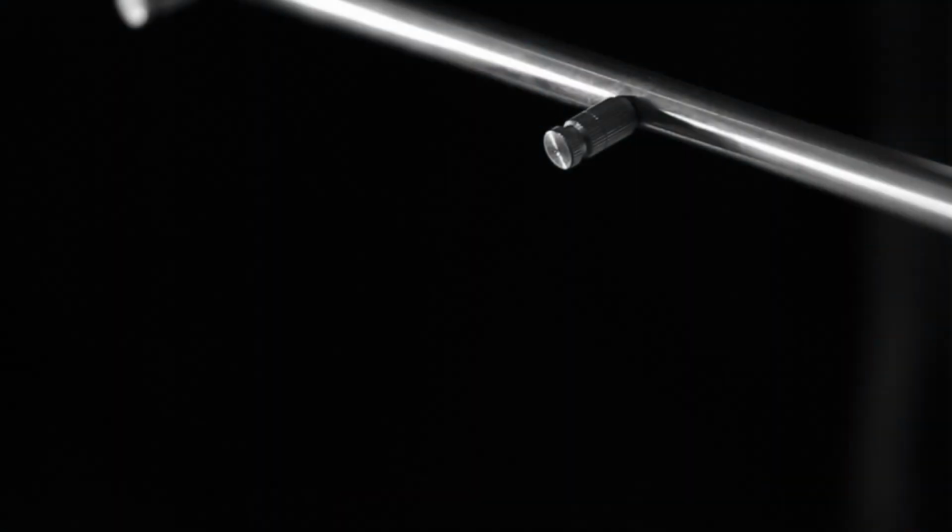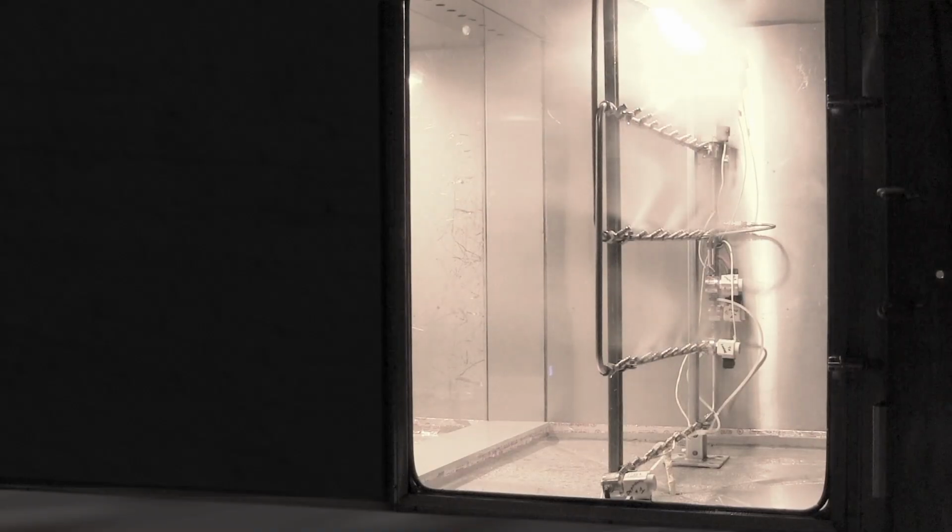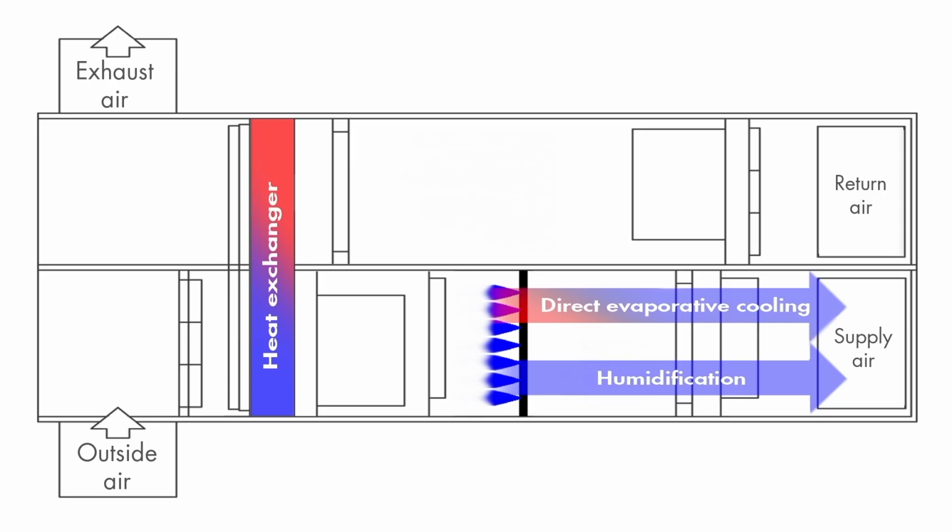Then it's also thinking through, okay, you mentioned cooling. Well, one of the things we didn't talk about is that instead of using steam, you can actually spray water in order to get that humidification. If you spray small water droplets into the air, it'll make it into the airstream. So you're humidifying. But that phase change has to happen to change it from water droplets into water vapor, which means you end up with a cooling effect of the airstream. It's taking energy out of the air. So it's a different way to think about it, but you're still adding the moisture. Instead of me adding steam and creating it initially, I have to take energy out of the airstream for water droplets.